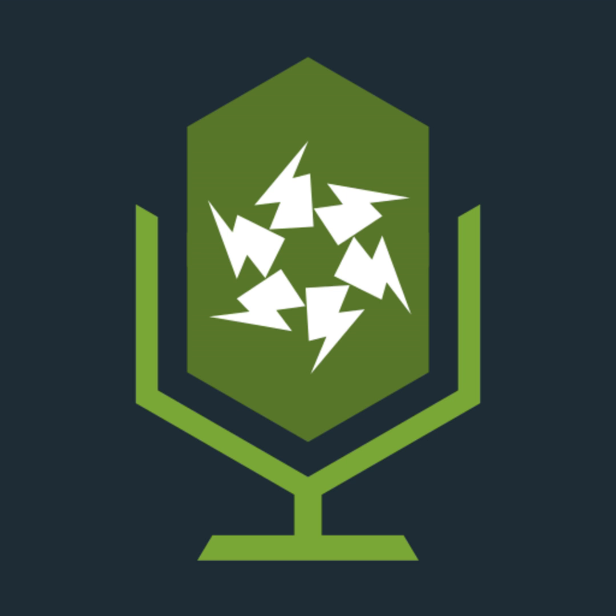So this is what I've got so far. S is the square root of I squared T over K, and I'm calling it IF because it's fault current. That's just how my head works. So that's 450 amp. Okay, the T. Now that amount of current, it tells me in this table, will achieve a 0.1 to 5 second disconnection. So I can call T 0.1, because it's going to disconnect in 0.1. And it tells me, back in 54, that T is the operating time of the protected device corresponding to the fault current. So the amount of time corresponding to that fault current is 0.1 seconds. So T equals 0.1 seconds.